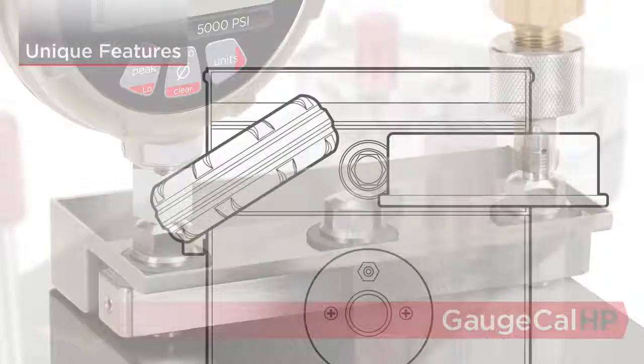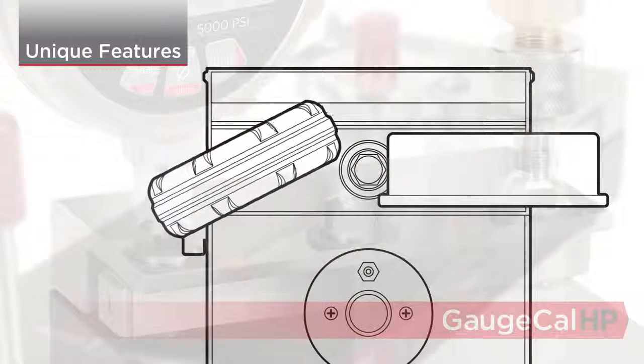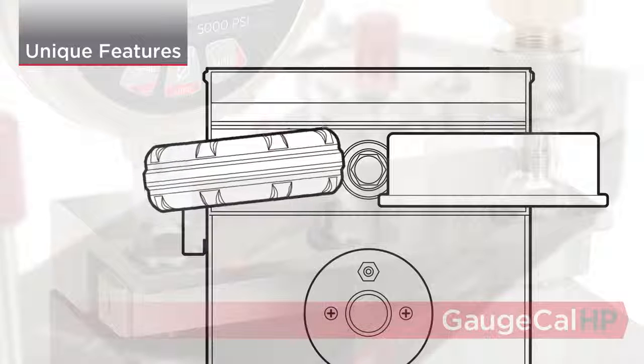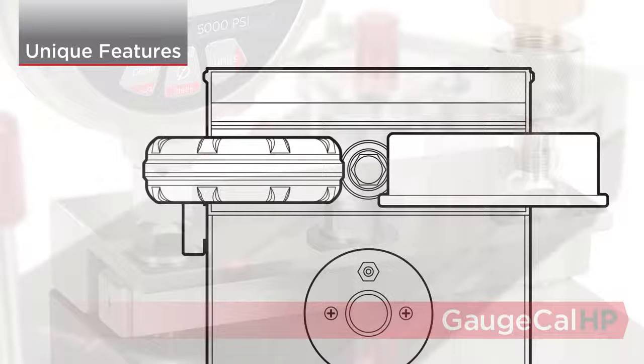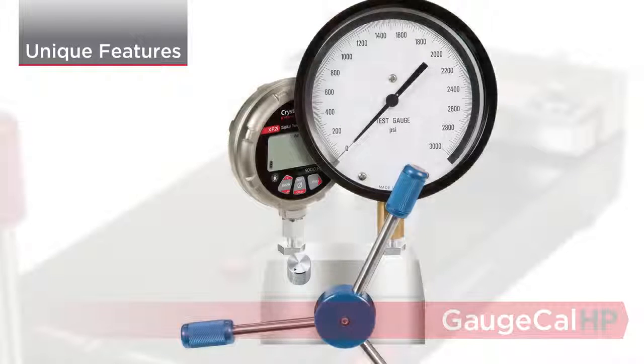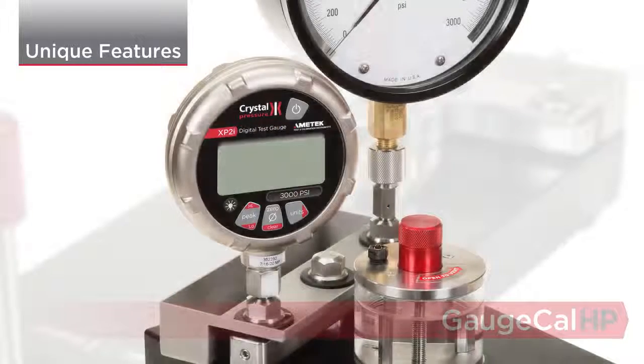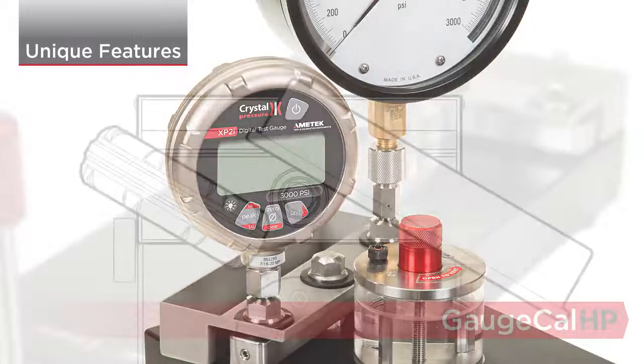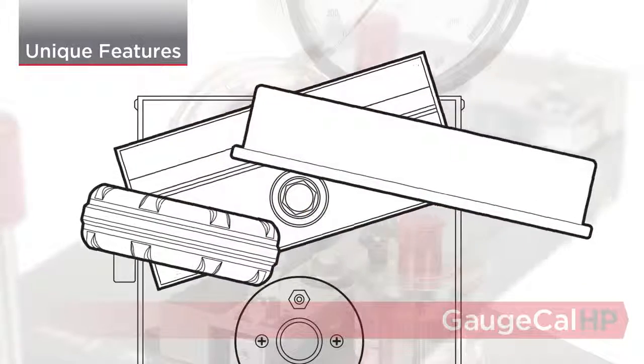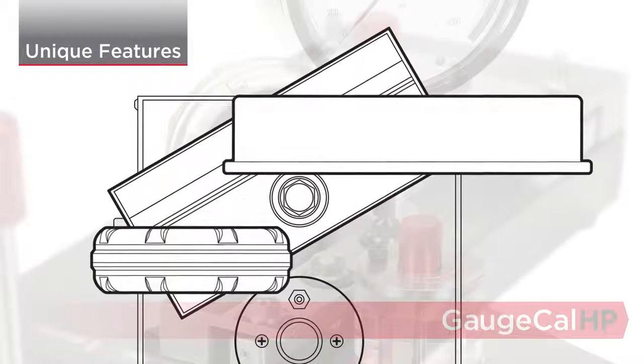If the gauges are not aligned after tightening, continue to turn the misaligned gauge clockwise and the port will swivel without loosening the connection. A common problem with other comparators is that large-sized gauges cannot be tested side by side with a reference gauge. The GaugeCalHP features a pivoting manifold system, which rotates to accommodate the extra space needed while keeping both gauges visible from the front.